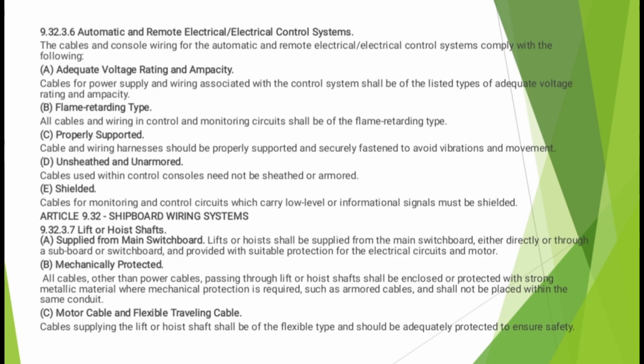Properly supported. Cable and wiring harnesses should be properly supported and securely fastened to avoid vibration and movement. Unsheathed and unarmored. Cables used within control console need not be sheathed or armored. Shielded. Cables for monitoring and control circuit may carry low-level or informational signals must be shielded.